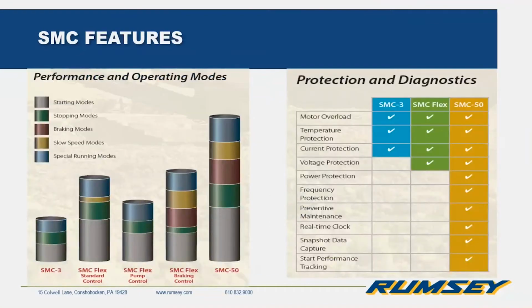And here's just an overview of the different features and kind of where they all stack up with each other. So the SMC3, again, as that being basic, has 4 different starting and stopping modes. The SMC Flex has some different control modules, a pump control and a braking control, but there's 8 different starting and stopping modes with the Flex. And then the SMC 50, that being the high end, has 10 different starting modes, 4 different stopping modes, and 4 different braking modes. So that being most capable. And then you see there on the right the different features. And again, the SMC 50 kind of standing out from the other 2.